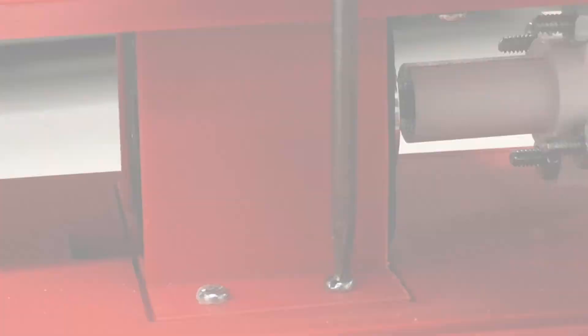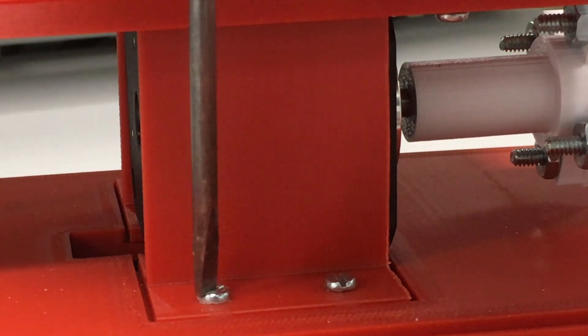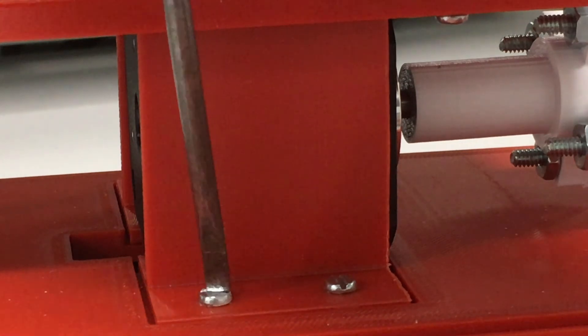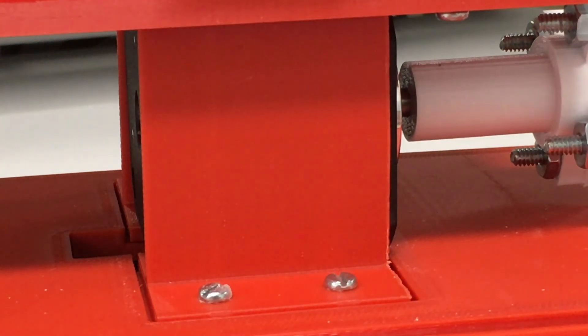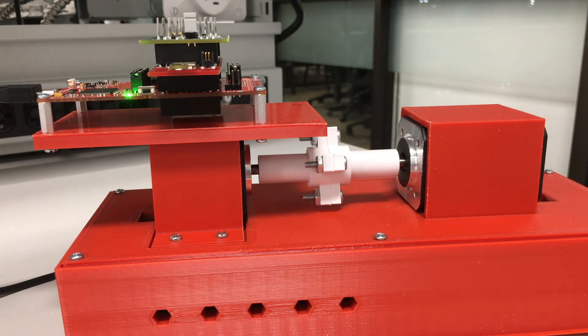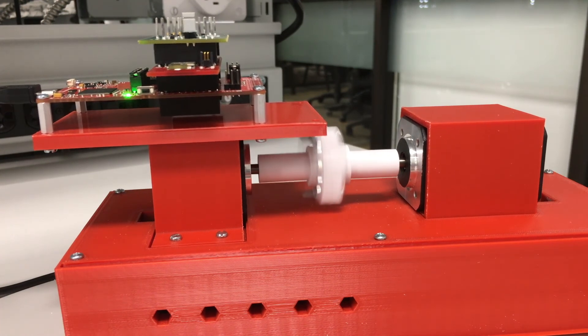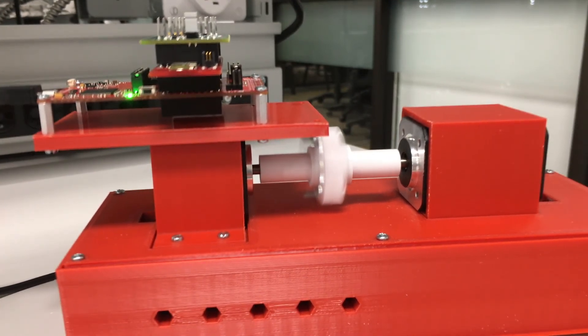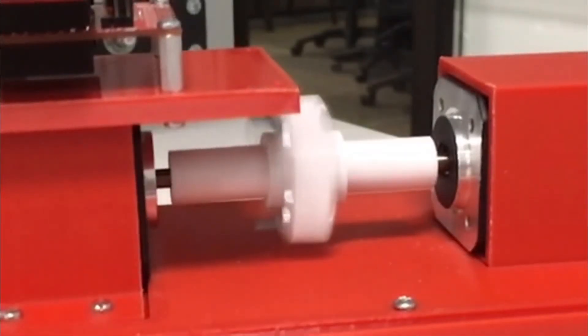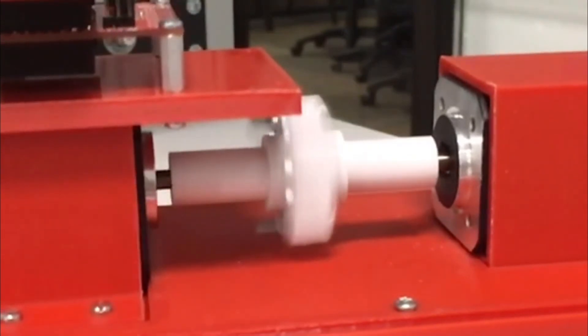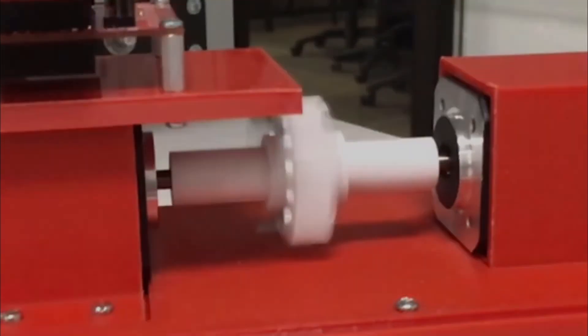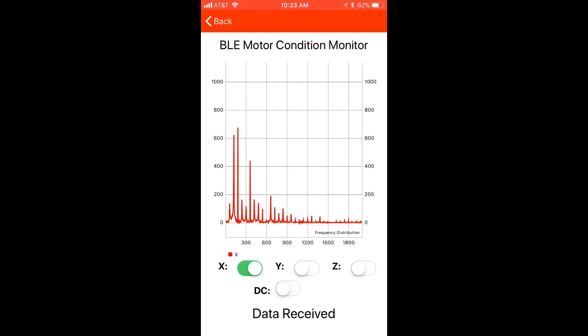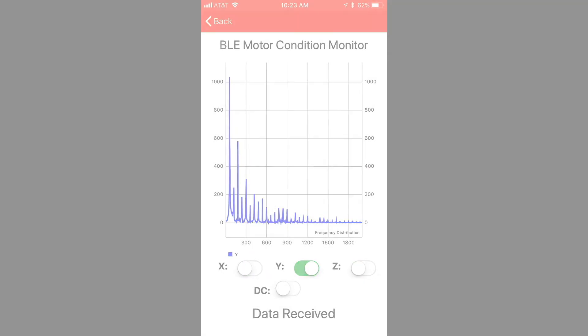With another failing setup, we shall now see how vibration patterns change. For this setup, we shall loosen the bolts holding down the test motor by half turns. At regular video speeds, we do not see much of a difference. However, as we slow down the playback, the loose motor mount is causing the wobble on the shaft. The output on the app shows that the energy is even more wideband than earlier.